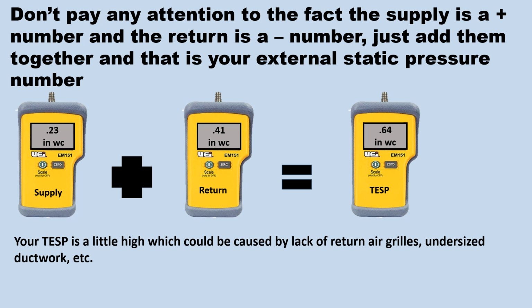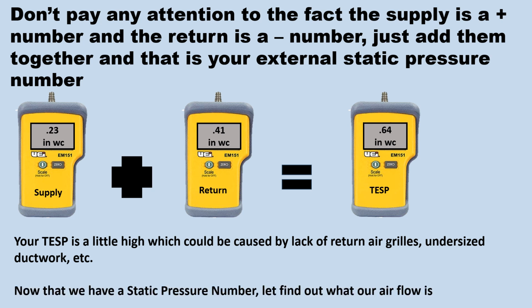But 99.9% of the time, it is the return. And the reason for that is cost engineering. Nobody goes around saying they're not going to put supplies in a room, but they will certainly go with as few returns as possible, and then the returns get undersized in duct sizing. But anyway, that's a little high. Now that we have a static pressure number, let's find out what our airflow is.